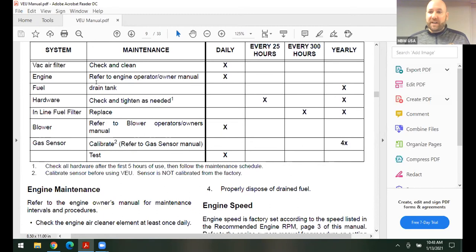And as Rick said, do the blower maintenance. Make sure you lubricate that blower. If you're pulling a lot of water or moisture, blow in 4 or 5 spritzes of WD-40 to lubricate those fan blades, which ensures the longevity of the blower itself. It's a quick, simple thing. For a couple bucks with a can of WD-40, it's a slam dunk to ensure the life of that unit.